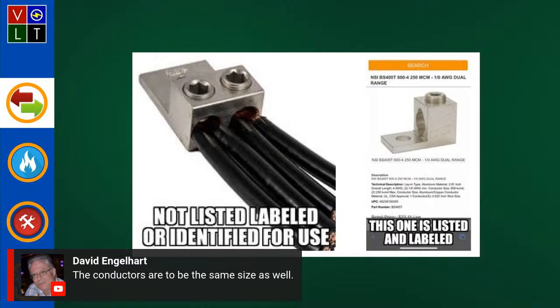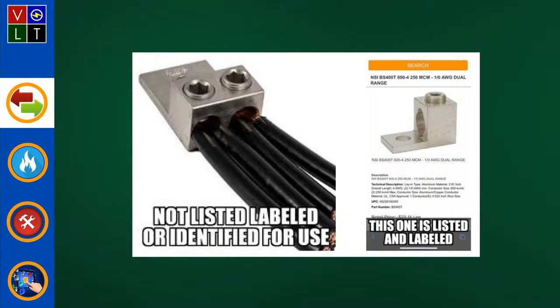I do agree with you, David. I'd say as a general rule the conductors have to be the same size, because I don't think it's going to make a really good connection otherwise. But I have actually done that before, with two different size conductors in a lug like this. We looked at it, and it didn't say anything that they had to be the same size. We had a small section and had to tap off with some number sixes as tap conductors, and there was nothing that said we couldn't do that. We went over it with the engineer, and he checked it out and said yeah, you're good, just get the correct torque on there and make sure those conductors don't come pulling out when you're done.